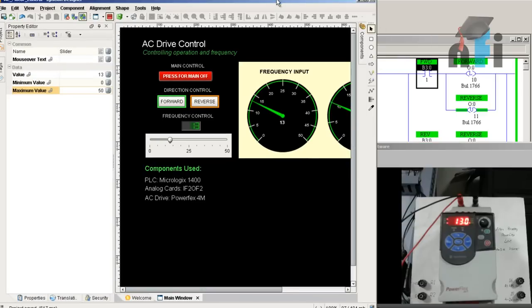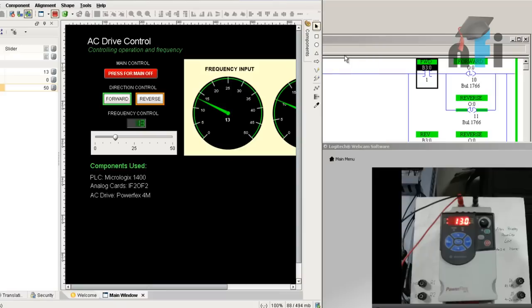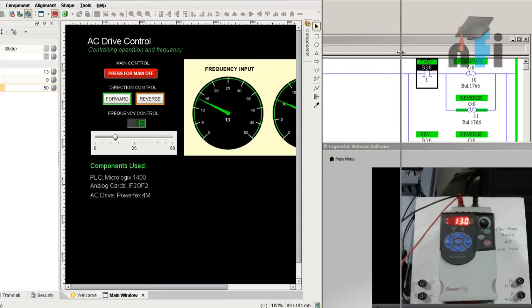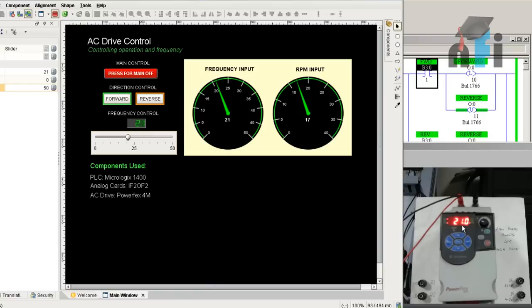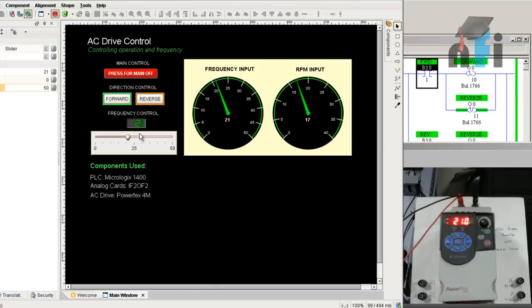Let me shrink that and show you the frequency variation. This is at 13 hertz. When I take it beyond, this is going to 21, so it will accelerate to 21. You can see 21 here and the RPM is 17 because the motor is rated 1350 RPM maximum but has a gearbox with gear ratio 40, so the RPM is 17.